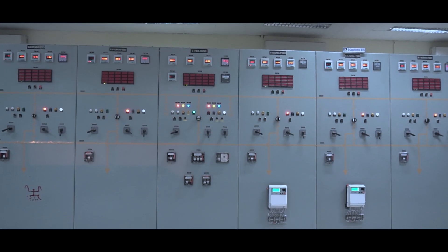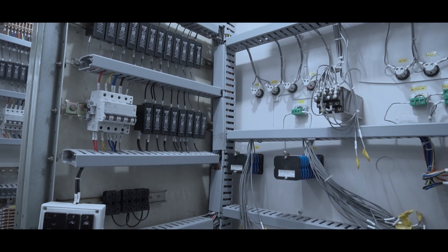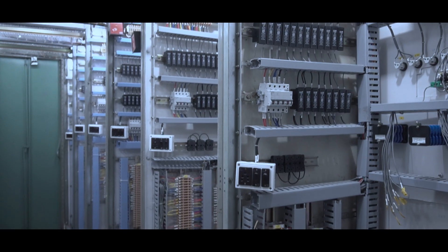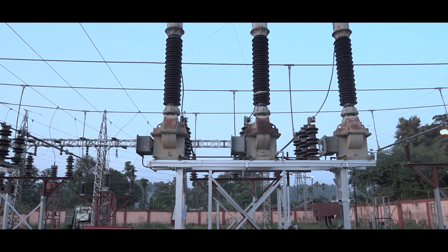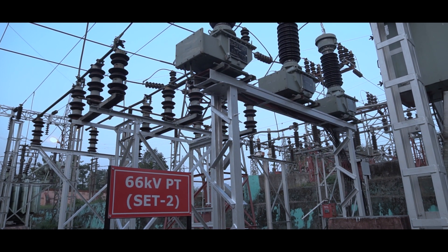Considering the importance of the 66kV system at the substation, the age-old 66kV control and relay panels were renovated recently. Work included incorporation of modern supervision scheme, rewiring, installation of new relays, meters, etc. To further improve flexibility and redundancy of the vital 66kV system, a second set of 66kV PT has been incorporated in the system.